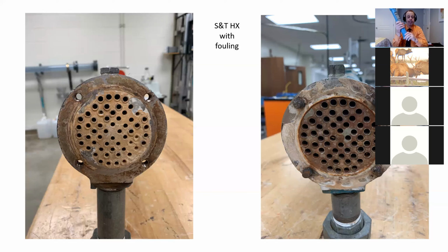That's also true if I'm doing... it's a little different if I'm doing phase change. If I'm using steam to heat things up, I want my steam to go on the shell side because it's very clean, and also because I want to form those condensate boundary layers over the tubes on the outside, like we talked about in chapter 23. It's a little harder on the inside to get a good film because it's horizontal, it would be dripping down weird. But on the outside, we're better at getting the H's. So mostly steam is almost always on the outside, the shell side.